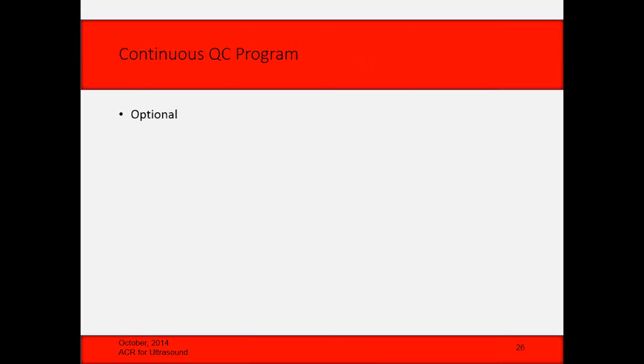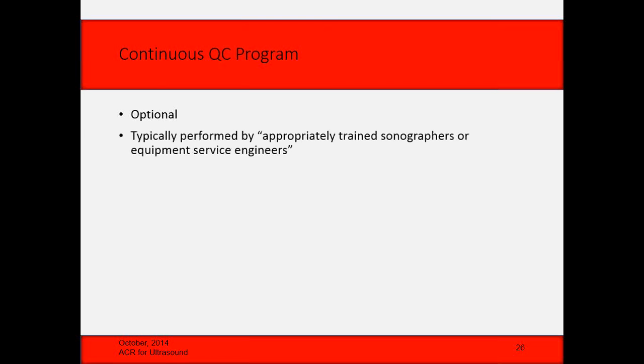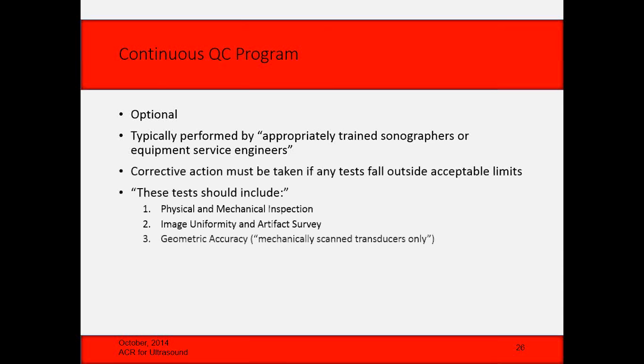So a continuous QC program is optional. I strongly urge you to adopt one if you don't have one already. It's typically performed by appropriately trained sonographers or service engineers. Corrective action must be taken if any of the tests fall outside the limits, of course. And the test should include physical and mechanical inspection, image uniformity and artifact survey. Geometric accuracy for mechanically scanned transducers only is what they say.